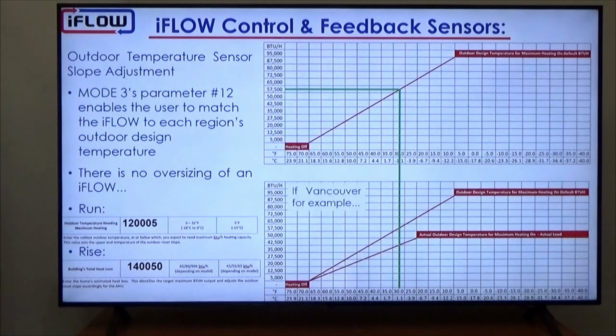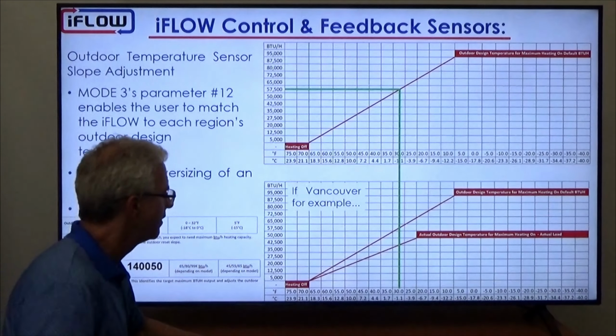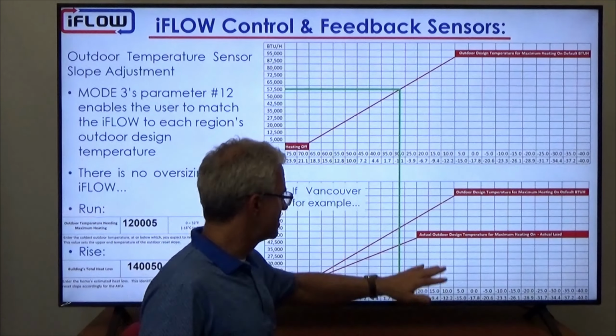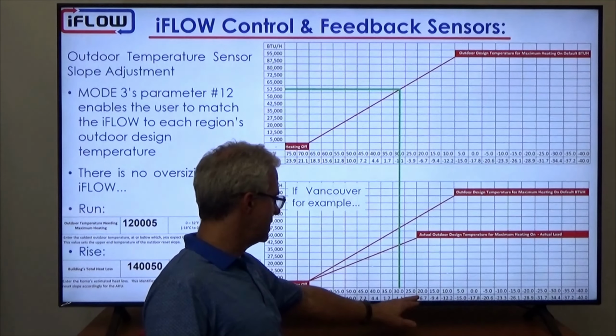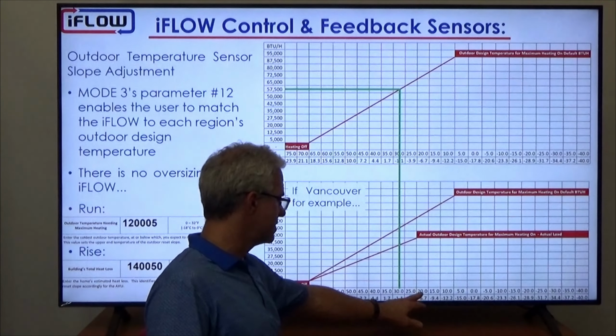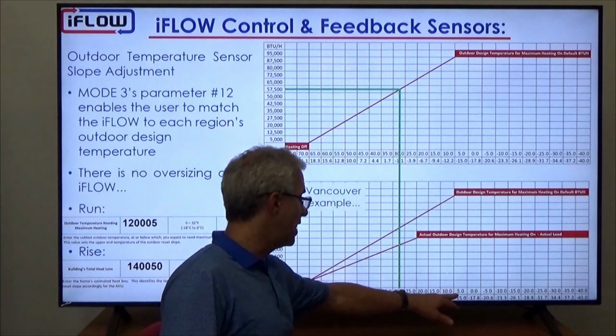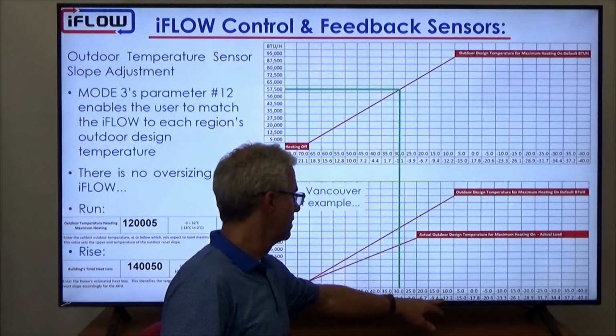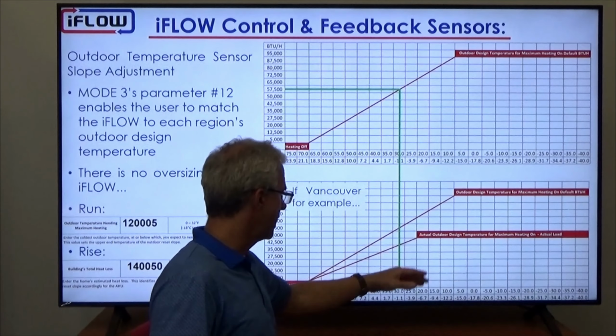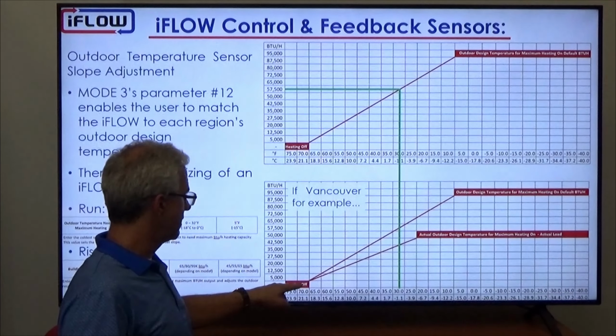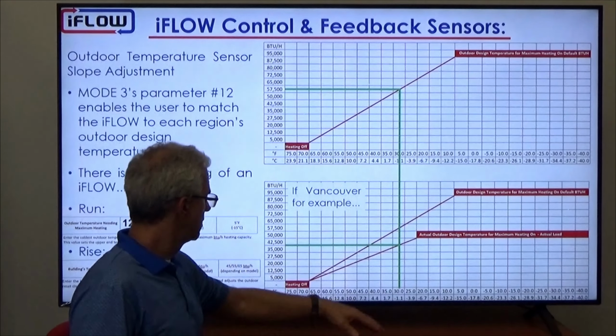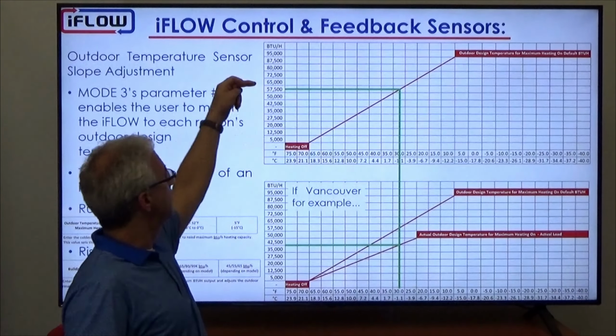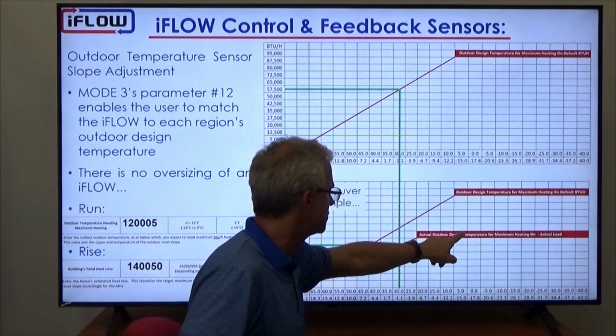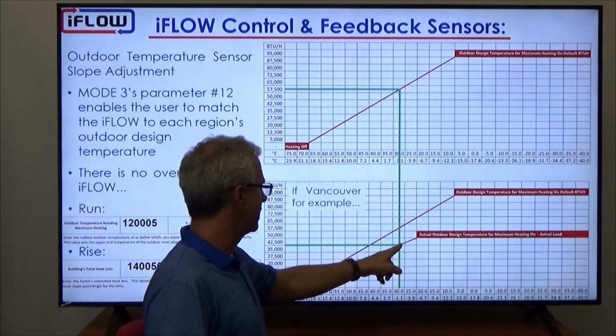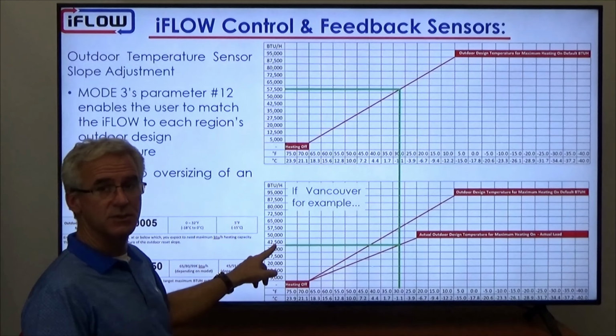So now, as I mentioned, we can adjust the outdoor design temperature. So if we adjust parameter number 12 to, let's say, if we're in Vancouver instead of Toronto, the actual outdoor design temperature is much warmer. So it might be 20 degrees, so it's minus 7 Celsius and not 5 Fahrenheit or minus 15. So we would then adjust it this way so that at a different temperature, right? Initially at 30 we were delivering 57,500, but because we've set the outdoor design temperature as a milder place, we're delivering less BTUs as you would expect.